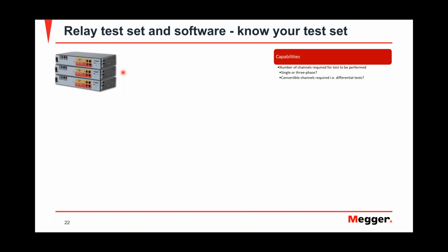Now, knowing your relay tester and the software that you have is another thing that you should always keep in mind. What are the capabilities of the tester that I have in my truck? How many channels are available for voltage and current? Are they going to be enough for the test that I'm doing? This one right here is actually a single phase test set, but we have 3 of them. Knowing that you could daisy chain them and get a 3-phase test set and a total of 6 currents, if you're doing a transformer differential.